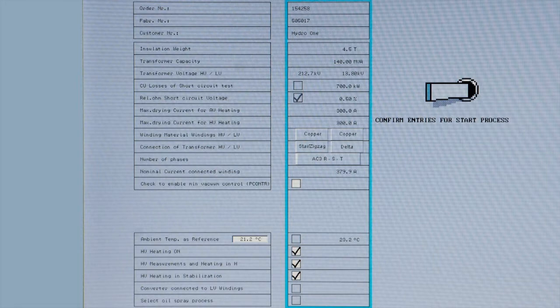Check to enable minimum vacuum control. Check this box if you want to limit the minimum vacuum value. This may be necessary if the transformer cannot withstand a substantial force resulting from the internal vacuum. Enter an appropriate value. Ambient temperature as reference. If the transformer is not at ambient temperature due to a previous heat-up, then a different reference temperature should be entered and used for the reference measurement stage.